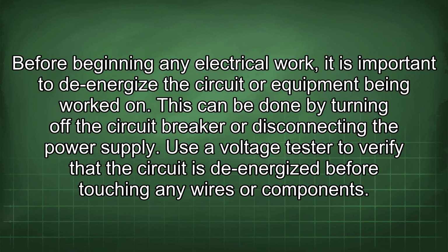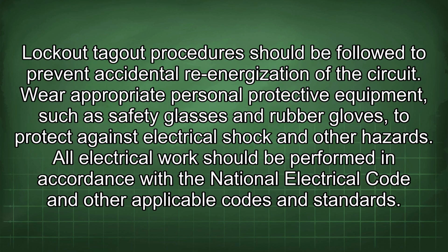Before beginning any electrical work, it is important to de-energize the circuit or equipment being worked on. This can be done by turning off the circuit breaker or disconnecting the power supply. Use a voltage tester to verify that the circuit is de-energized before touching any wires or components. Lockout-tagout procedures should be followed to prevent accidental re-energization of the circuit.